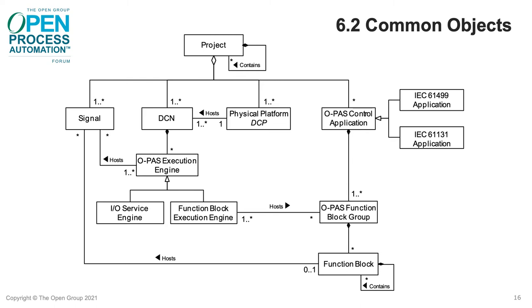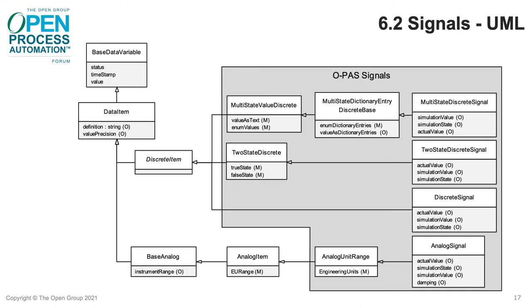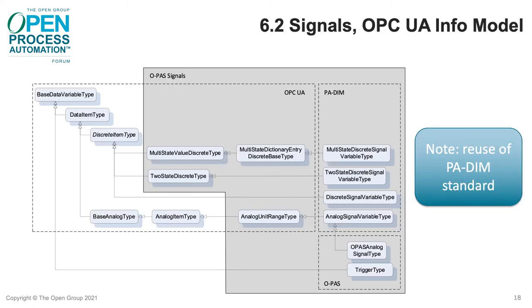Here is a UML diagram of some of the main objects defined by Part 6.2 of the OPAS specification. Here's a UML diagram showing how OPAS representation of signals derives from the base OPC UA variable types, and the same picture using OPC information model syntax makes clear that OPAS signals are compatible with PA-DIM signals. PA-DIM is a standard for process automation devices information model, used to represent temperature, flow, level, pressure, valve positioners, and similar things on OPC UA.